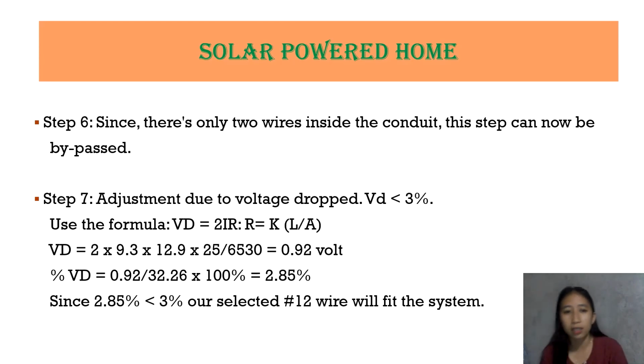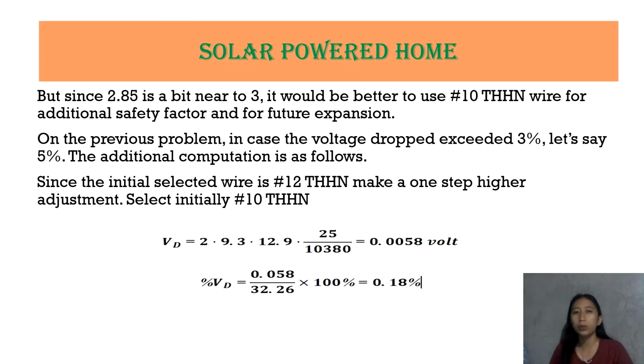So, VD is equal to 0.92 over 32.26 times 100%, which is going to a total of 2.85%. Okay, so since 2.85% is less than 3%, our selected wire is number 12, which can be fit into the system. Okay, but since 2.85 is a bit near to 3, it would be better to use number 10 THHN wire for additional safety factor and for future expansion.